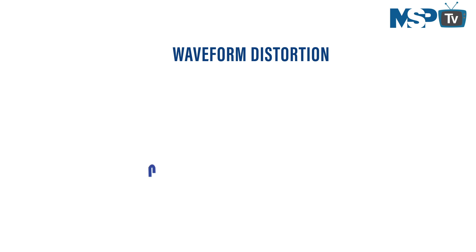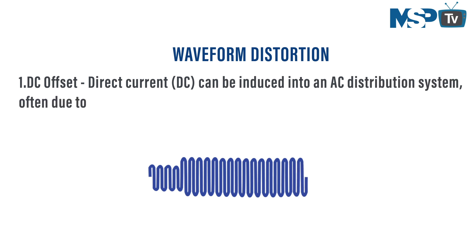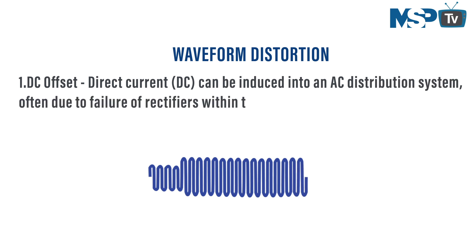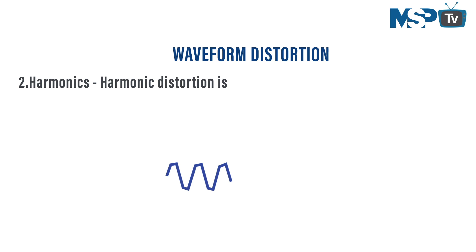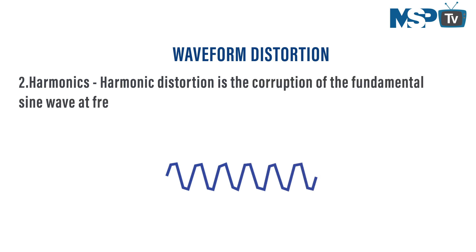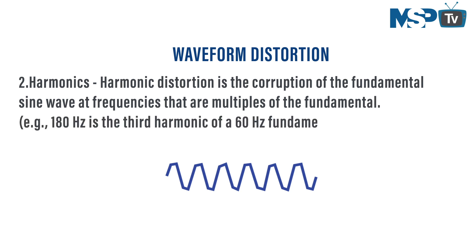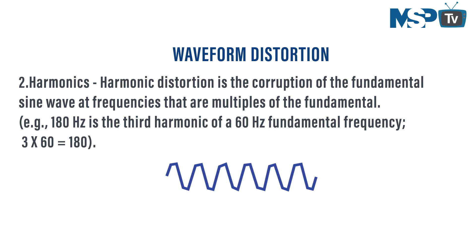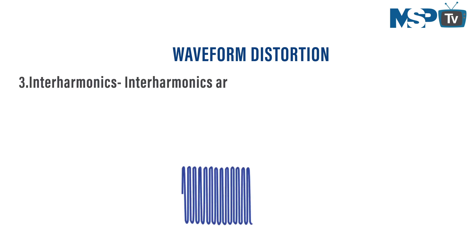The fifth problem is waveform distortion, which has five types. First, DC offset: direct current can be induced into an AC distribution system, often due to failure of rectifiers within AC-to-DC conversion technologies in modern equipment. Second, harmonics: harmonic distortion is the corruption of the fundamental sine wave at frequencies that are multiples of the fundamental — for example, 180 Hz is the third harmonic of the 60 Hz fundamental frequency, which is 3 × 60 = 180.